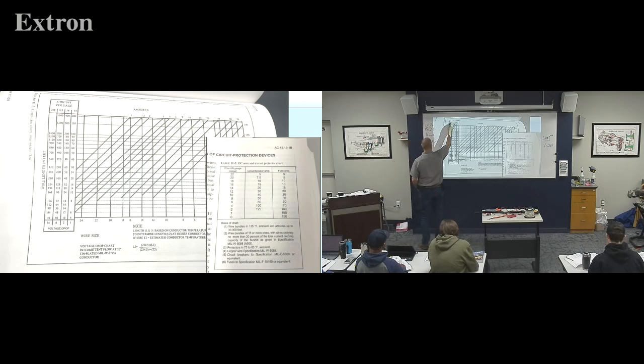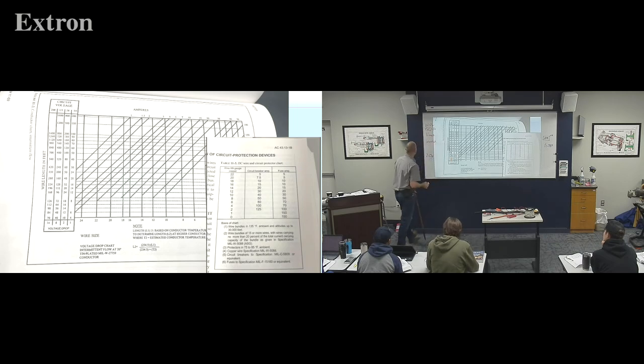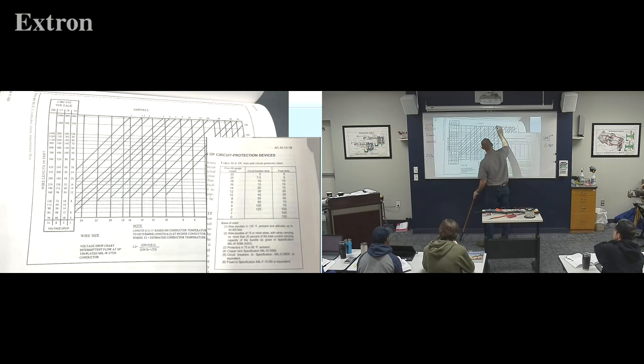200 volts, 150 foot, so we're somewhere in between, aren't we? And we'll get that a lot - 126, 168 - I'm gonna go with right about here. 150 foot, double-checking ourselves, intermittent, yep. All right, 10 amps, so 10 amps - it's nice when it falls right on the line, because then you can circle it and your students don't laugh at you.